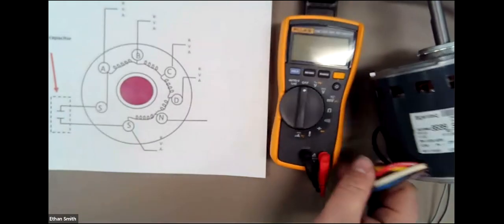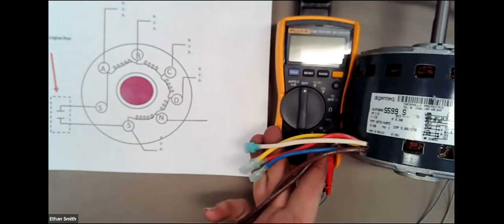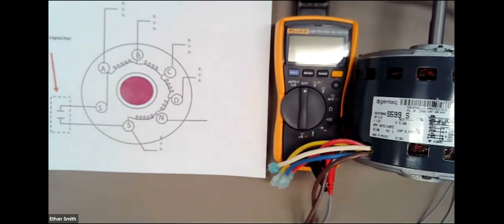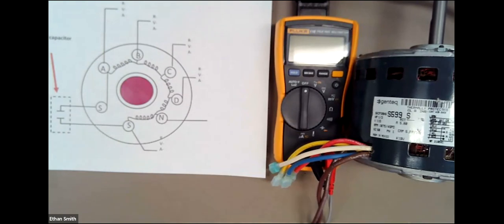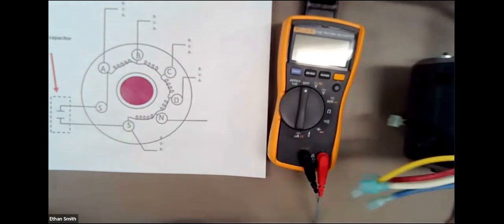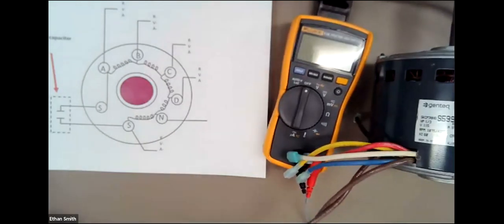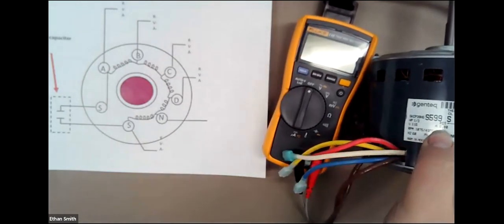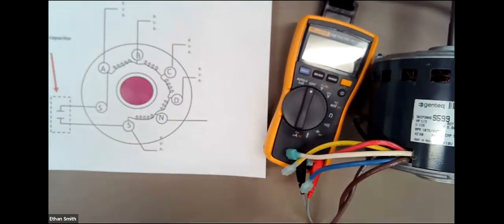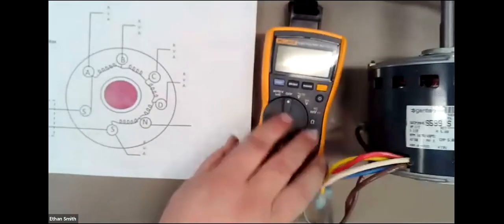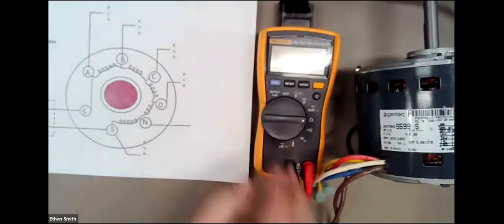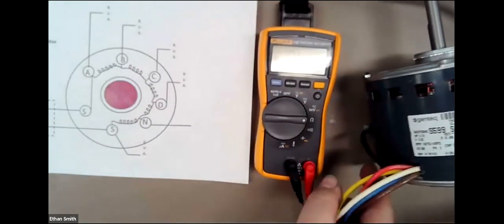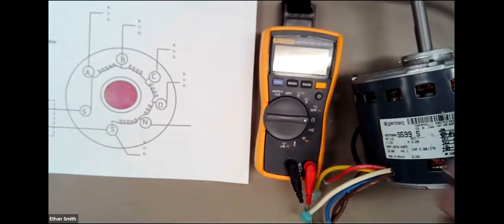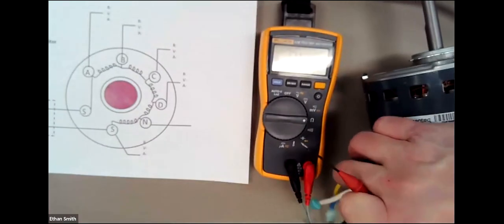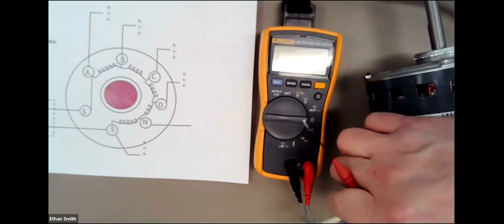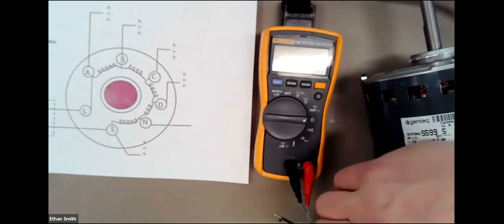We've got an electrical meter, and we've actually got that motor that's in that drawing. Okay, so it's got a permanent split capacitor motor here. I think we've got the right capacitor on it. I've got a 5. Is that a 5 microfarad? Yes. Okay. This is just like a little blower motor that we would have in a furnace. But have any of you ever walked up to a blower motor in a furnace and there's no wiring diagram, there's no nameplate on the blower anymore, you don't know what the speeds are? Has that ever happened to anybody?